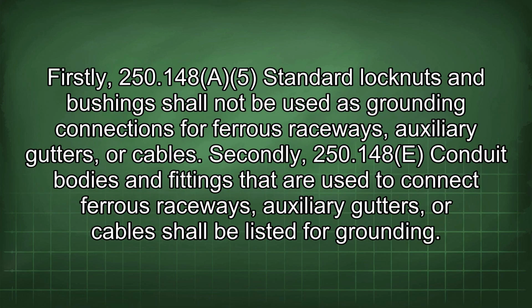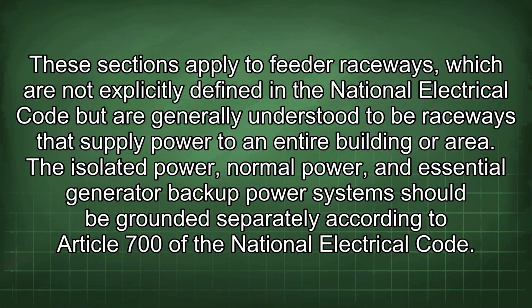Firstly, 250.148: standard locknuts and bushings shall not be used as grounding connections for ferrous raceways, auxiliary gutters, or cables. Secondly, 250.148: conduit bodies and fittings that are used to connect ferrous raceways, auxiliary gutters, or cables shall be listed for grounding. These sections apply to feeder raceways, which are not explicitly defined in the National Electrical Code but are generally understood to be raceways that supply power to an entire building or area.